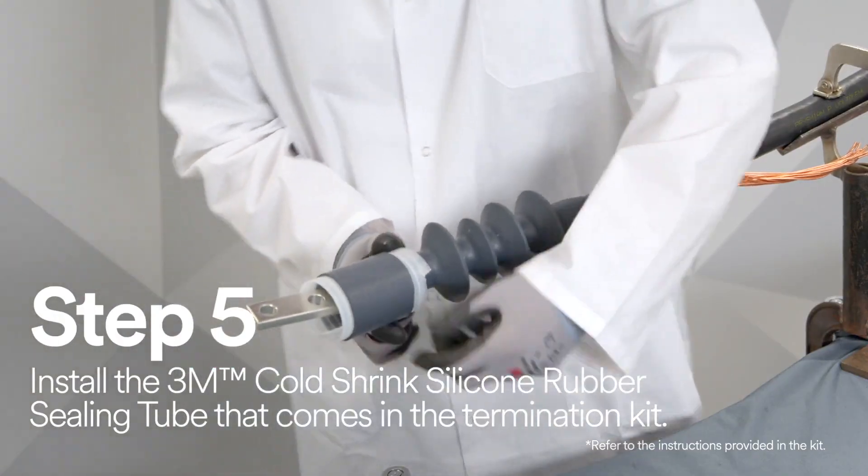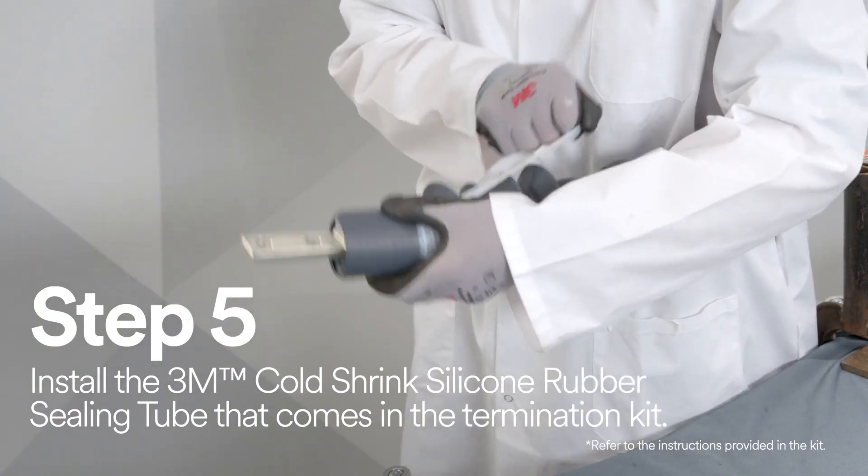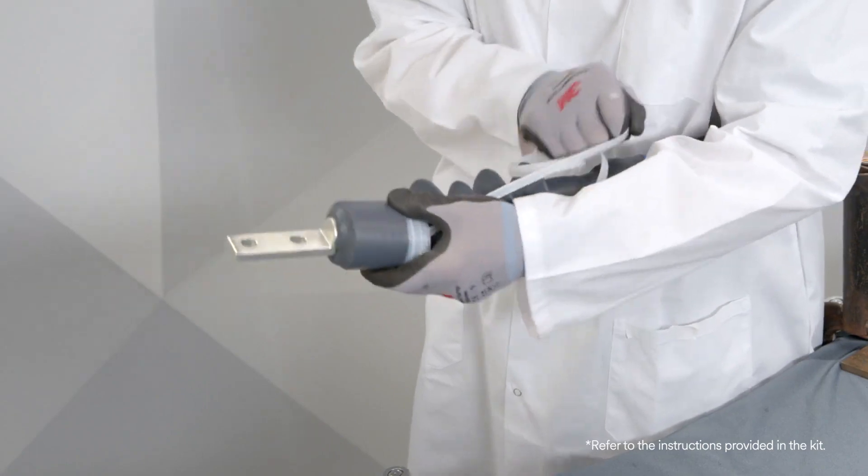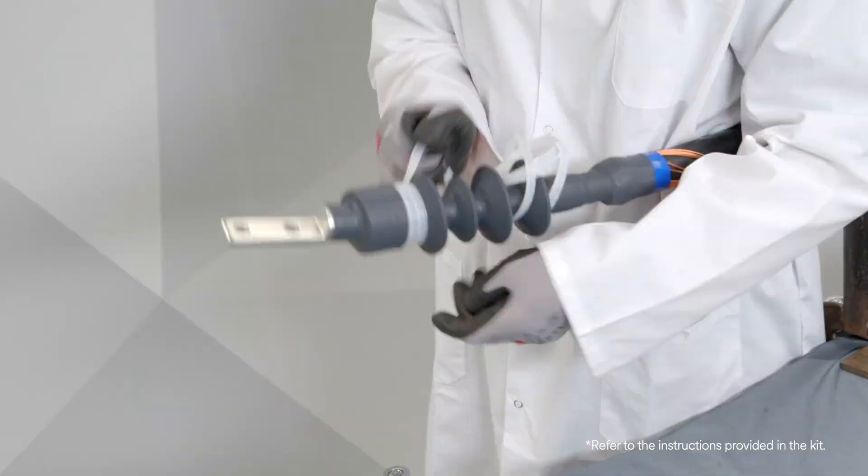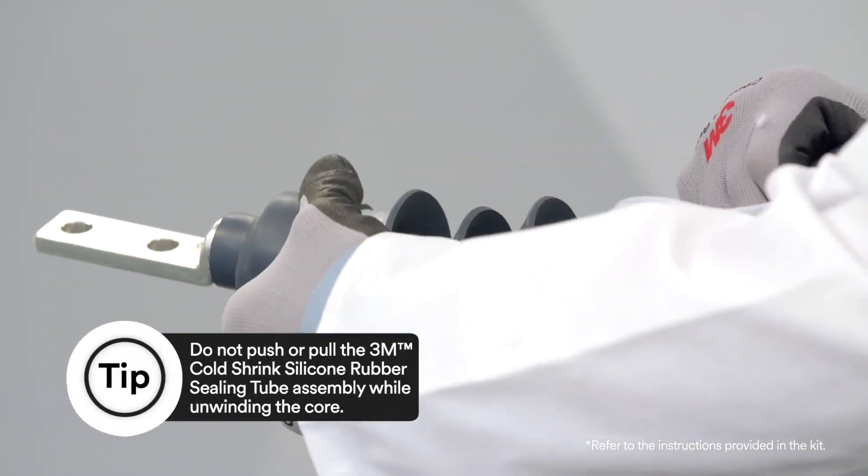Install the 3M cold shrink silicone rubber sealing tube over the foil tape by aligning the edge of the 3M cold shrink silicone rubber sealing tube, not the core, with the lug body edge closest to the connection holes. The loose core end will be facing towards the cable and termination assembly.